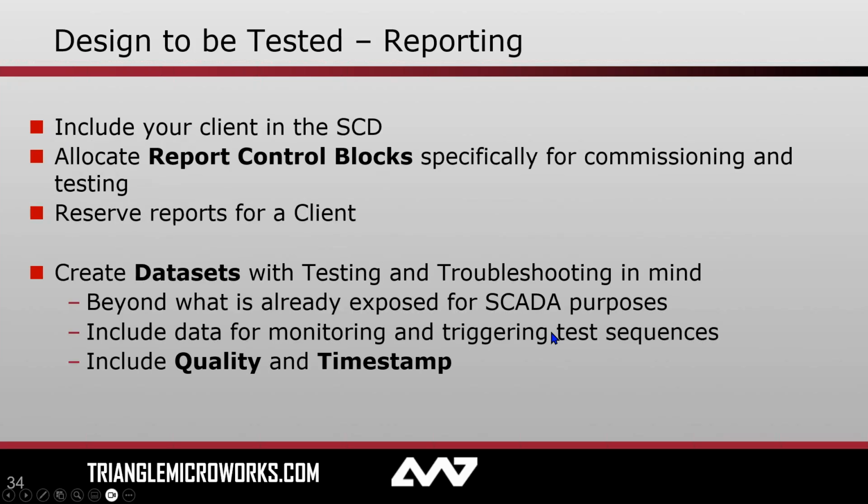So beginning with reporting. When I'm talking about designing to be tested, and specifically in the context of reporting, it begins with including your clients in the SCD file. Typically when we include clients in an SCD file, we're talking about SCADA systems, right? So maybe your gateway or a local HMI, but also your testing client. Typically, testing tools fall in the category of client, even though they might be subscribing to Goose or even in some cases publishing during testing scenarios. But in 61850 terms, something like Test Suite Pro or similar tools would be classified as a client.